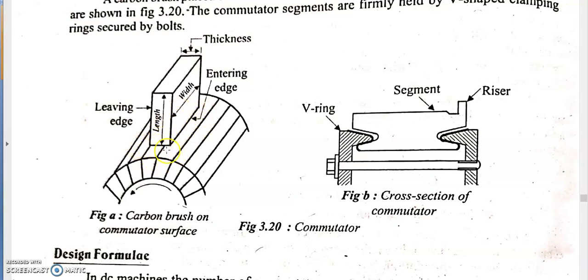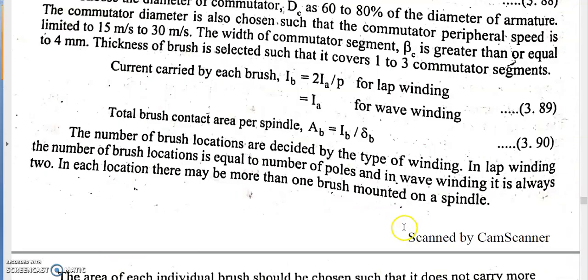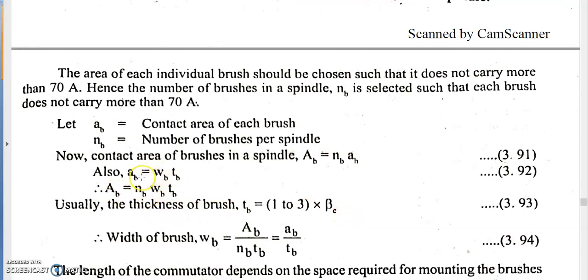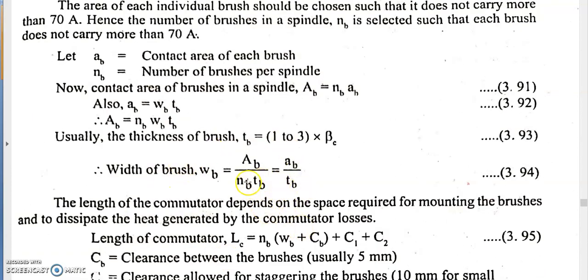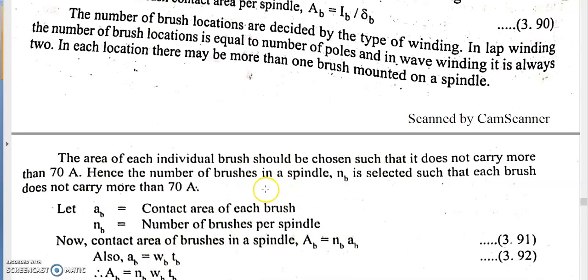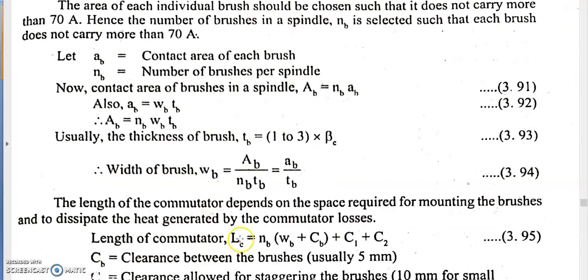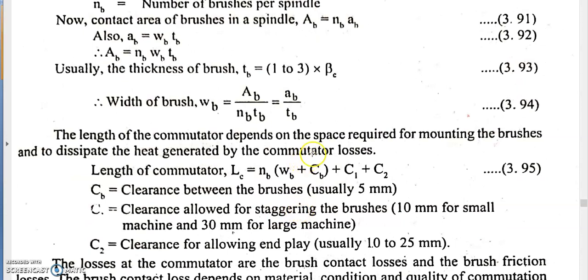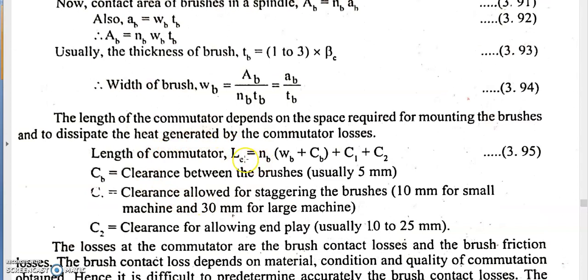The dimensions of the brushes — thickness, width, and cross-sectional area — are now determined. Finally, the length of the commutator LC is calculated using the formula: LC = NB × (WB + CB) + C1 + C2, where NB is the number of brushes, WB is the width of the brush, CB is the clearance between brushes (5 mm), C1 is the clearance for staggering the brushes, and C2 is the clearance for end play.